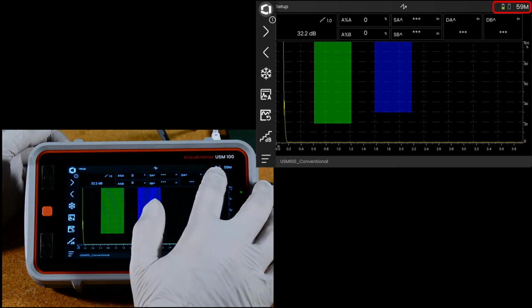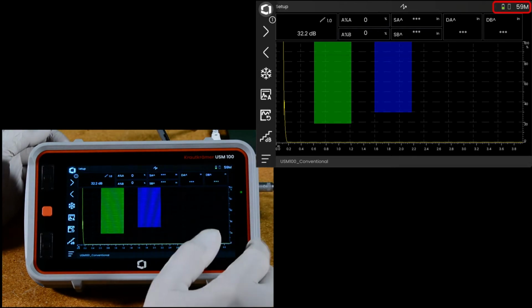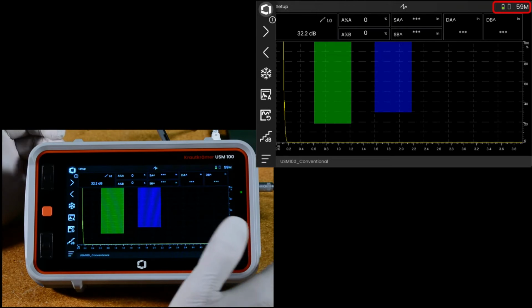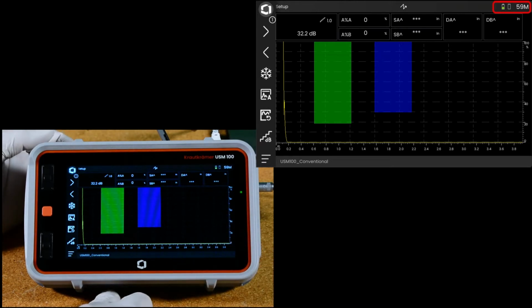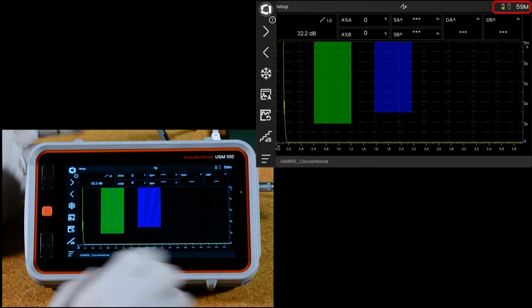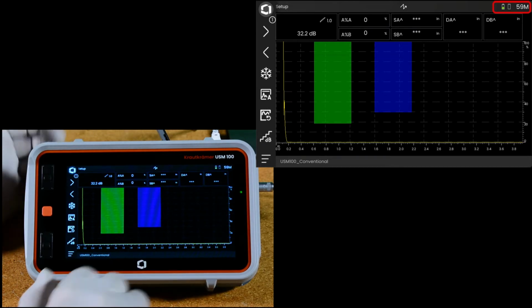Over here on the upper right-hand corner is the battery status monitor. There are 2 little graphical indicators, one for each of the batteries. There are 2 batteries in this instrument. One is built in permanently. The other is accessed through a door here on the bottom. You can hot swap that one. While the instrument's in operation, you can open the door, pull that battery out, put in a freshly charged battery, and you're ready to continue operation.